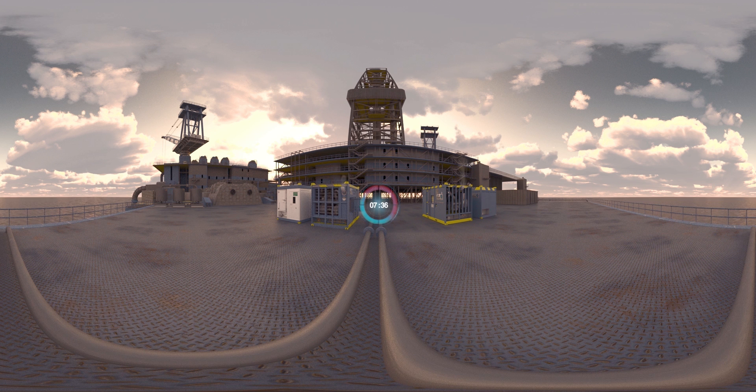Both compressor types are rated to deliver 1600 CFM at 150 PSI and require permanently open ventilation during use. Operating at full load, Zone 2 compressors will have a maximum surface and exhaust temperature of 200 degrees centigrade, compared with more than 600 degrees for a rig-safe unit.